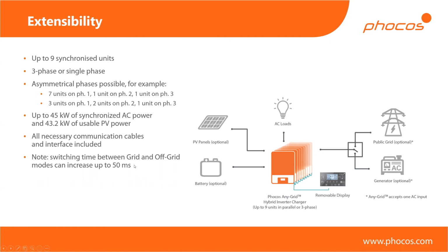There is a small caveat if you're using more than 1 unit, and this is less pronounced on a single-phase system, a little bit more pronounced on a 3-phase system. The switching time increases from 10 milliseconds to up to 50 milliseconds. Like 50 milliseconds is the worst-case scenario. Typically, it'll be somewhere between 10 and 50 milliseconds. Again, most computer power supplies will handle power outages up to 50 milliseconds. So we are still within spec for the majority of your loads.